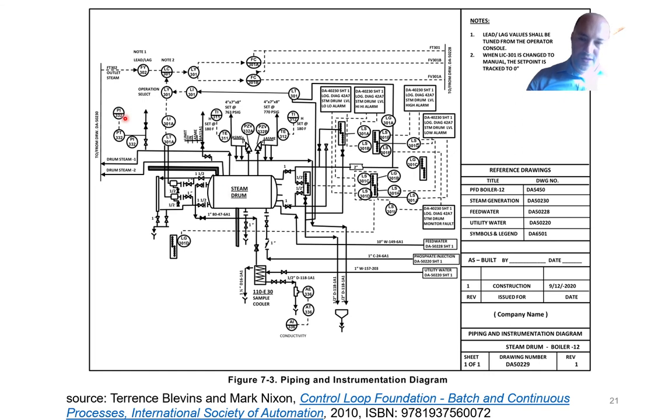Okay, here I have PI, pressure indicator. So this means that I'm showing some pressure somewhere. This would be my pressure transmitter. So this is what senses the pressure. They all belong to the same circuit, 332. So this is this one circuit. I have a local indicator of pressure. I have a pressure transmitter, so this transmits me some signal, and this goes to a panel that is displaying me the pressure on some panel in the control room.